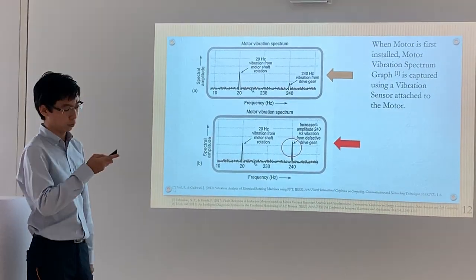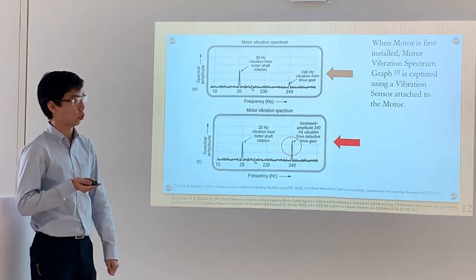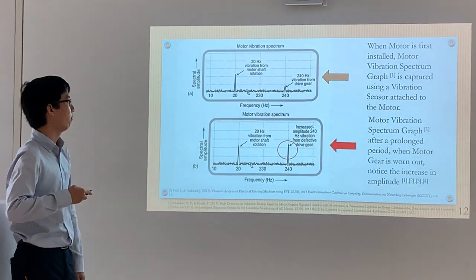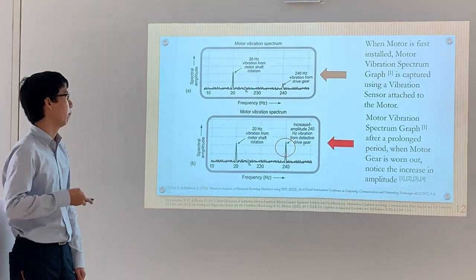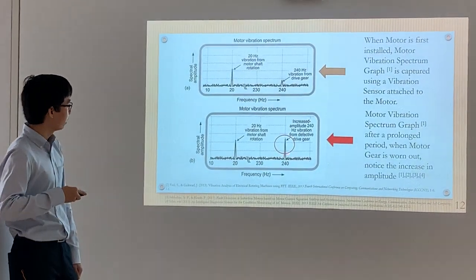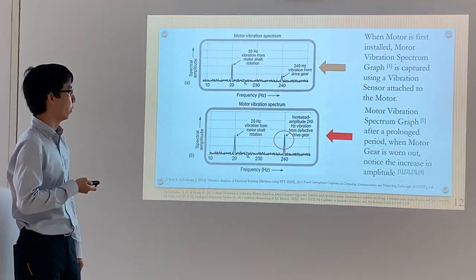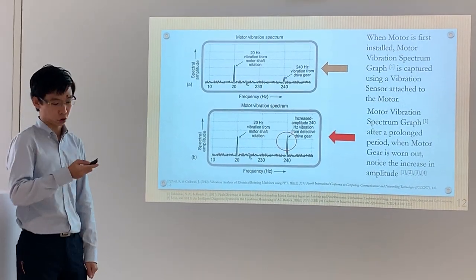The first graph shows when the motor was just installed. The vibration spectrum graph is captured using a vibration sensor attached to the motor. After a prolonged period when the motor gear is worn out, you can see the increase in amplitude. This research through IEEE papers has come to the same conclusion.